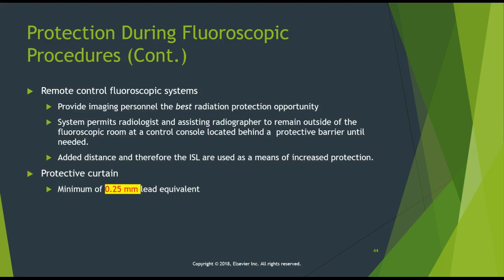Okay, now one of the things they talk about that is going to help protect you is called a remote control fluoro system. This provides imaging personnel with the best radiation protection. The system allows the radiologist and the assistants or radiographers to remain outside of the fluoro room at a control console, which is located behind a protective barrier until you are needed. Okay, now unfortunately, this doesn't get utilized a lot because we have made our practice of our fluoro exams being in the room with the patient, doing things as the fluoro is on. Okay, so you don't see remote control being utilized a lot. Since that is the case, you need to add distance and use the inverse square law. That's going to increase your protection in those rooms.